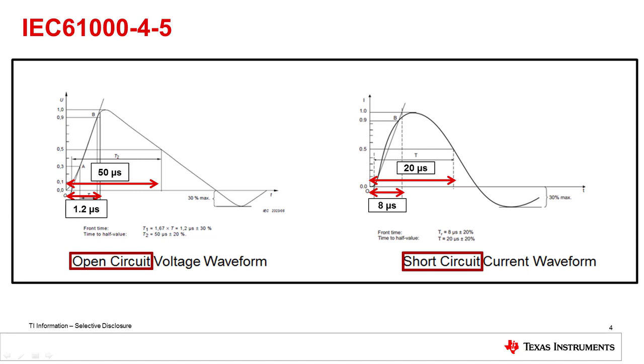The surge tester, by definition, has a 2 ohm output impedance, so the voltage peak waveform will be twice the magnitude of the current waveform peak. To pass the IEC 61000-4-5 standard, a system must have this waveform applied to the system inputs with no damage sustained.